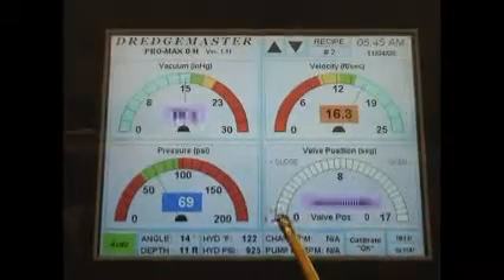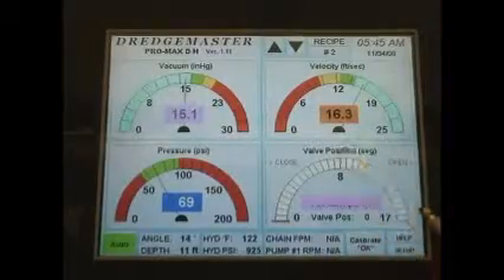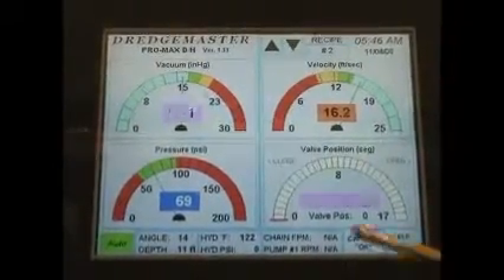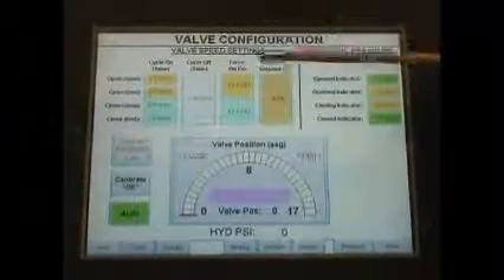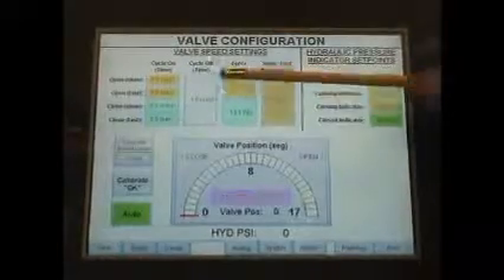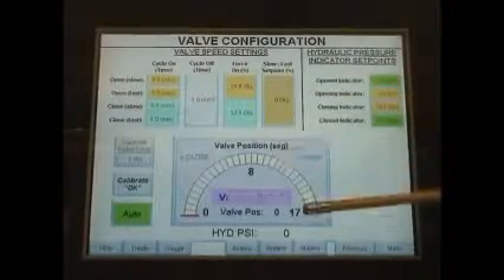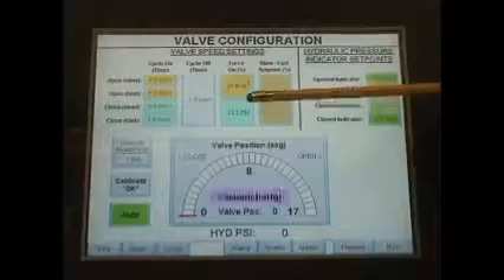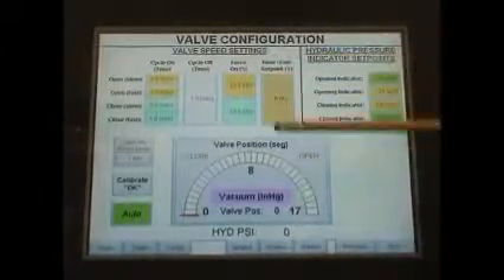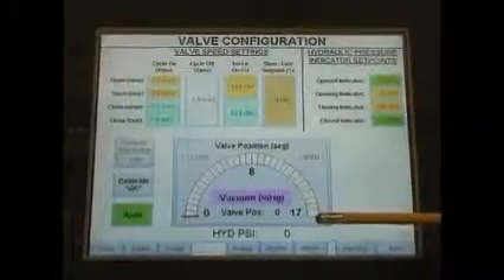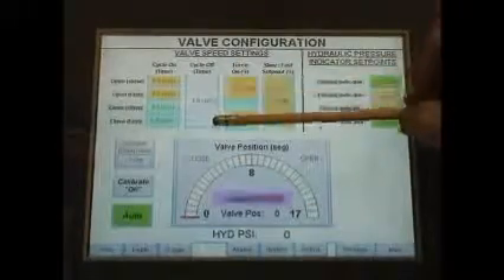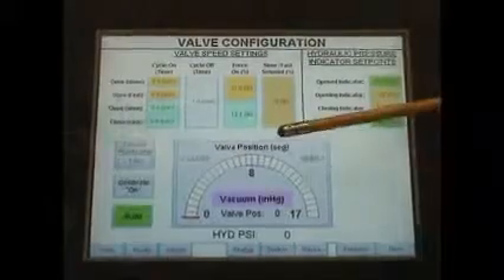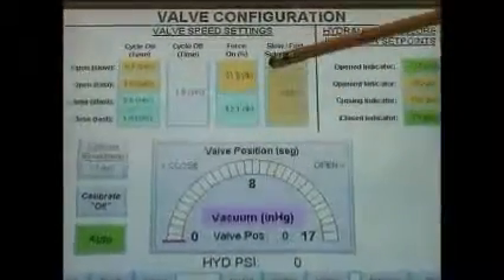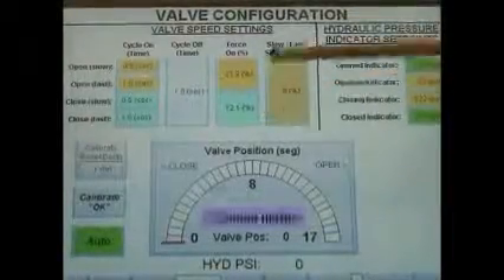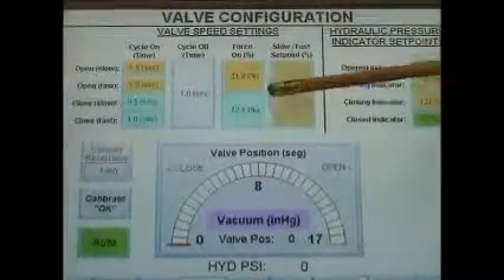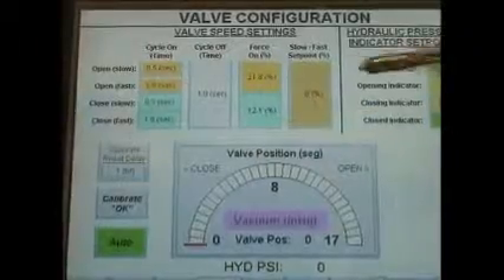Okay, calibration okay. Now it's going to take 17 hits to fully open up the valve. In other words, it's going to take a little longer for the valve to go from fully closed to fully open. As you can see, our force percentage has changed. The computer automatically set up the percent of force to get 17 segments going open, and it automatically calculated what percent of force it needed to go closed, so that if it takes 17 segments to open the valve, it's also going to take 17 segments to close the valve. And that's the difference in our force percentage. A hydraulic cylinder uses less oil going closed than it does going open, due to the fact you have the area of the rod inside the cylinder taking up volume, so it has to move less oil to go closed than it does in an open.